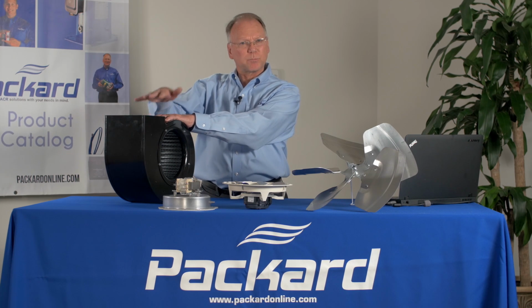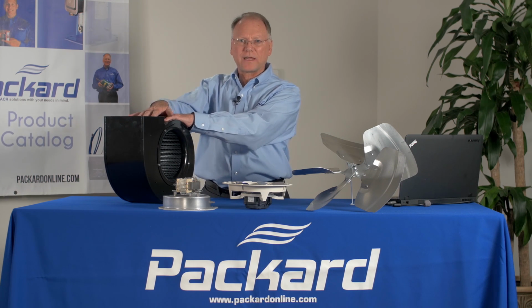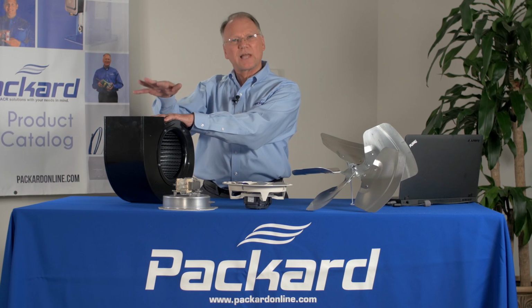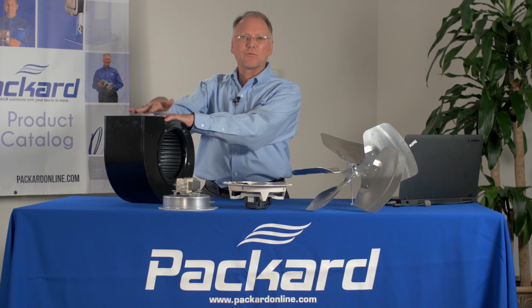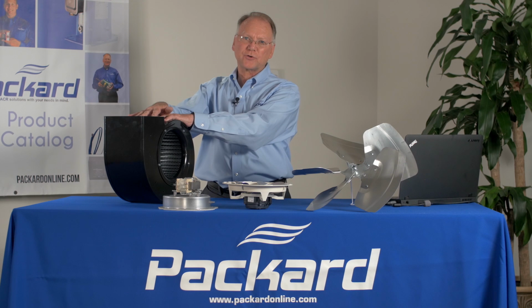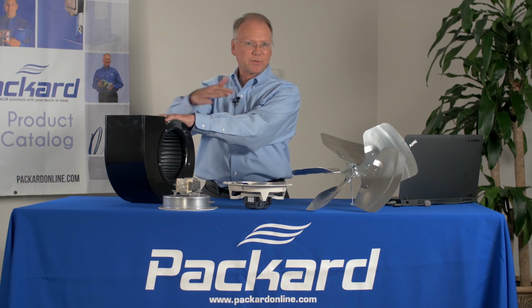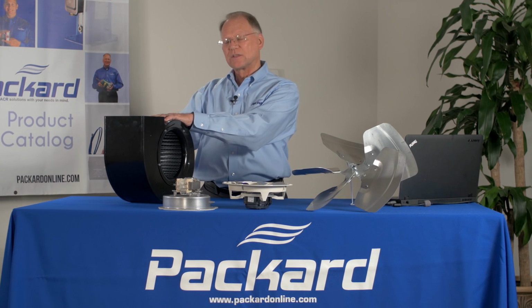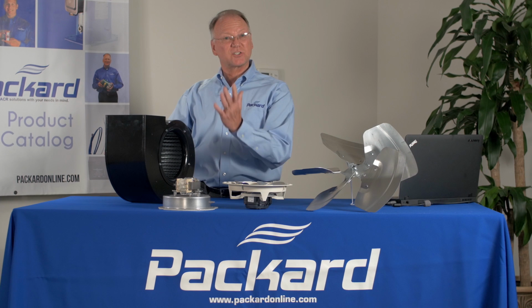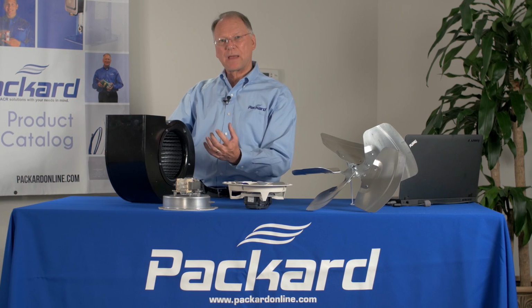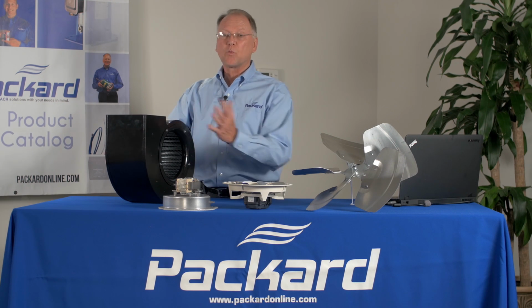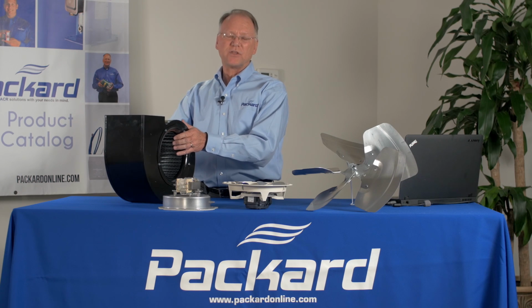Now, the reason the blower is used rather than a fan is because that blower can overcome more static pressure than what the fan blade can. The static pressure is just that, it's static. That is the amount of pressure on the system without movement of the air.